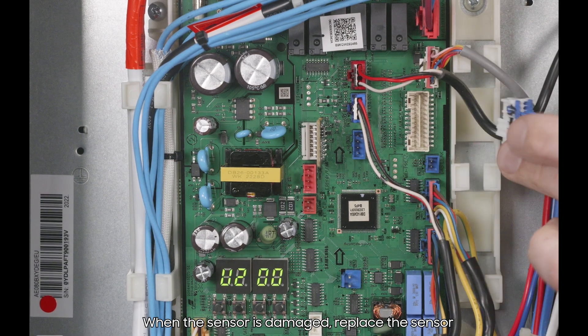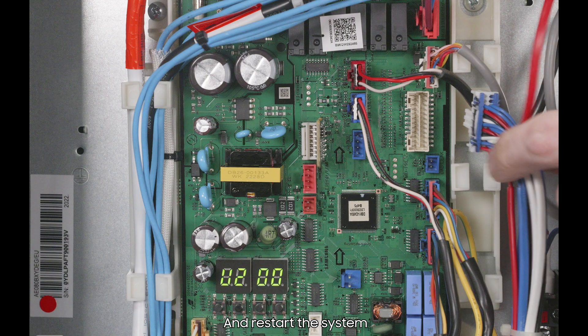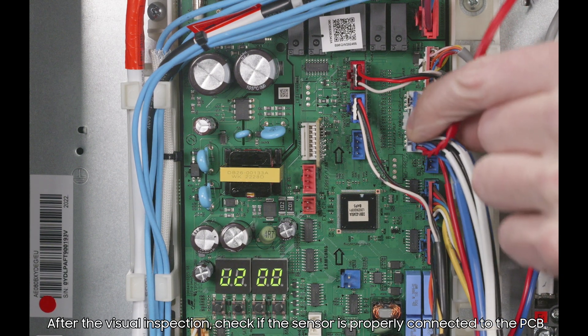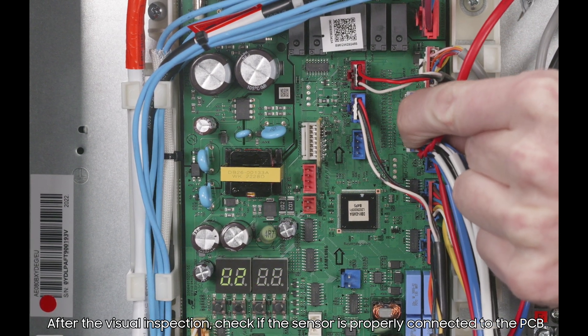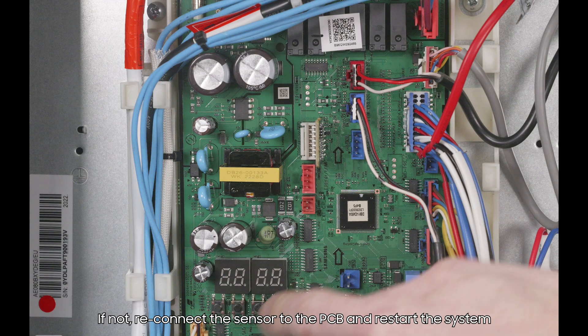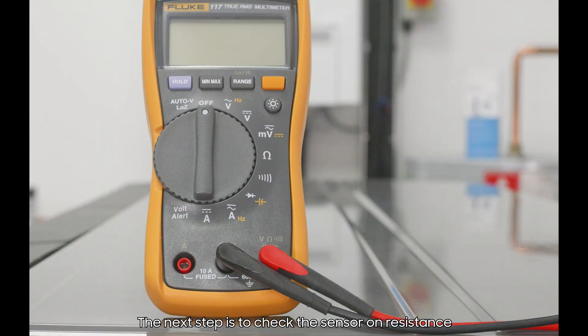When the sensor is damaged, replace the sensor and restart the system. After the visual inspection, check if the sensor is connected properly to the PCB. If not, reconnect the sensor to the PCB and restart the system.